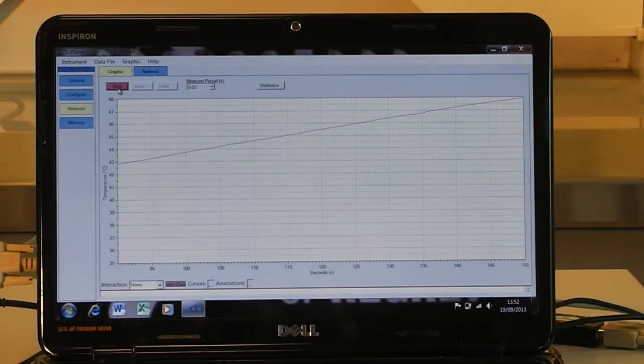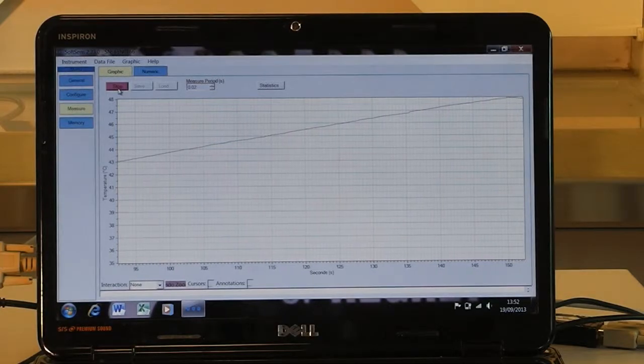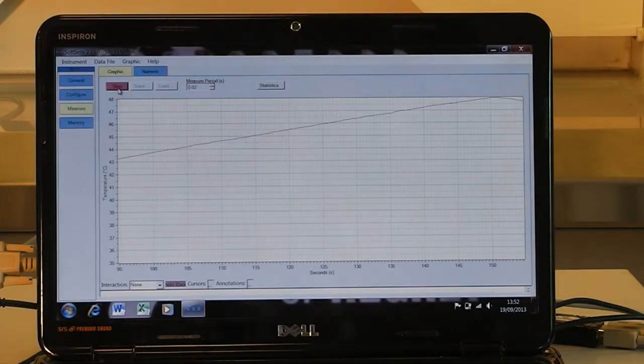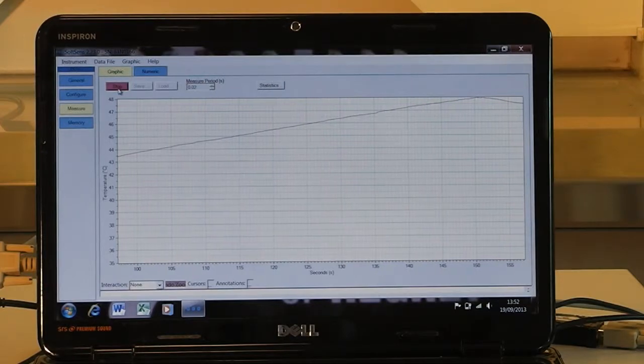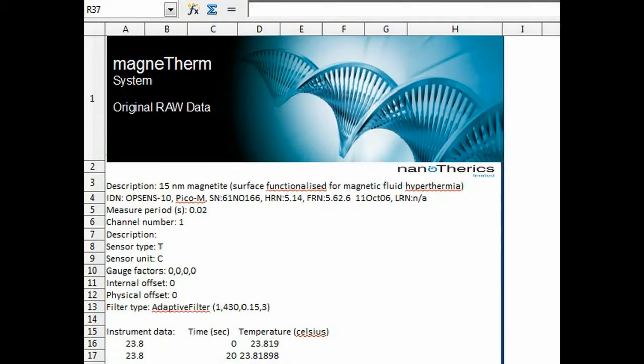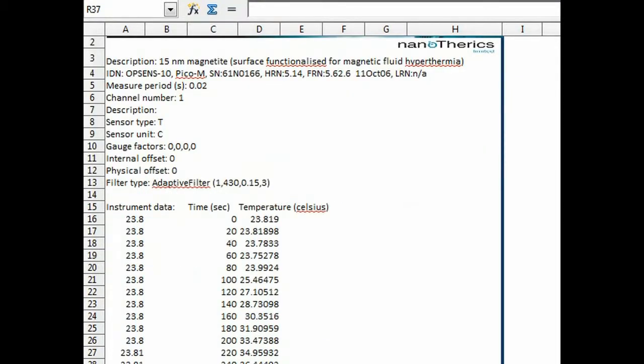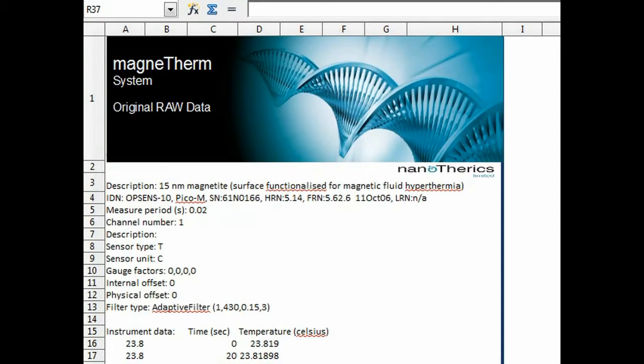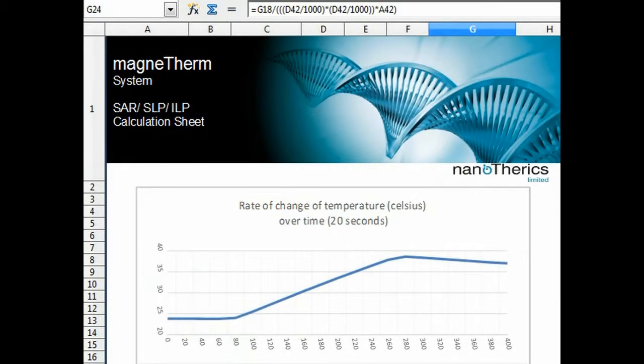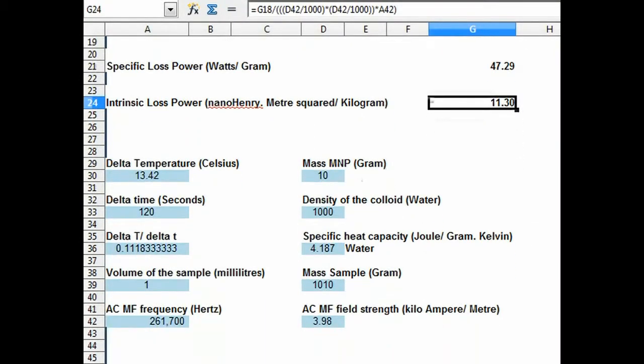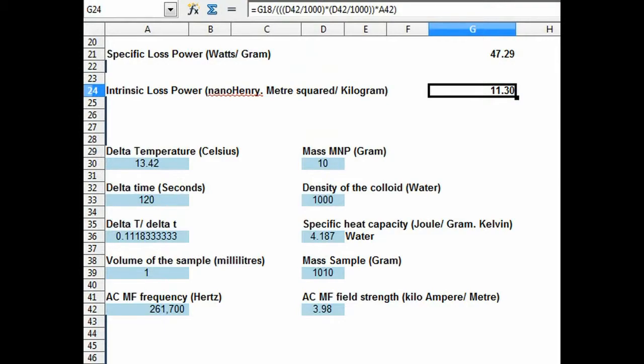The power loss calculation program will provide the specific absorption rate, specific loss power, intrinsic loss power values for the test sample and facilitate the user access to the raw data in Excel format for further interpretation. The calibration liquid, i.e. 20 mg per mil concentration of 50 nanometer size maghemite provided with the system will show an increase in temperature over time, allowing the user to view magnetic nanoparticle heating in an AC magnetic field.